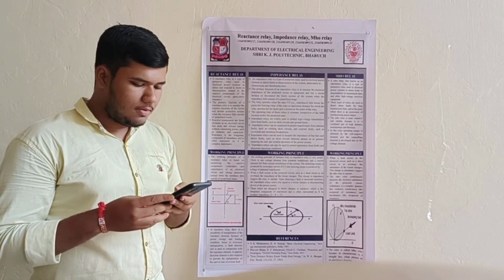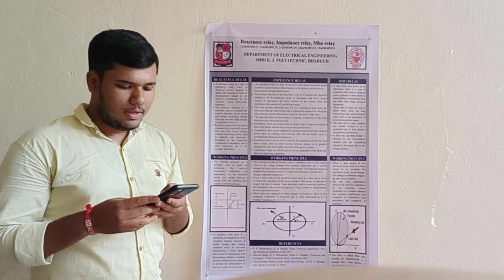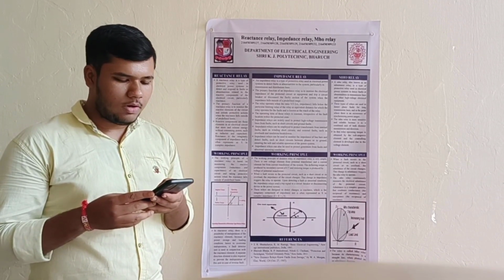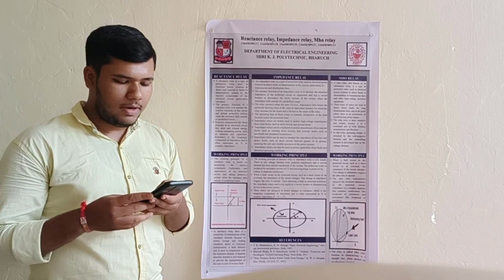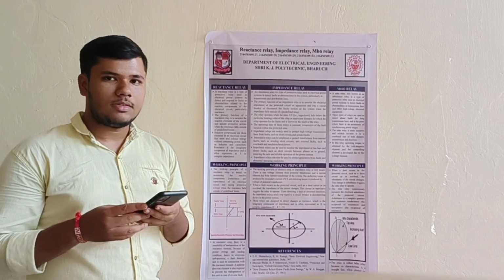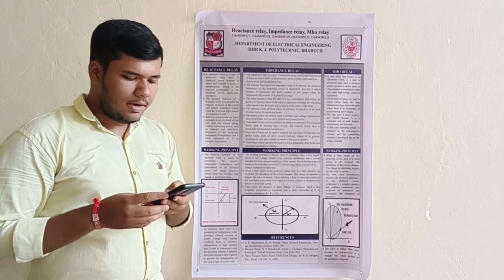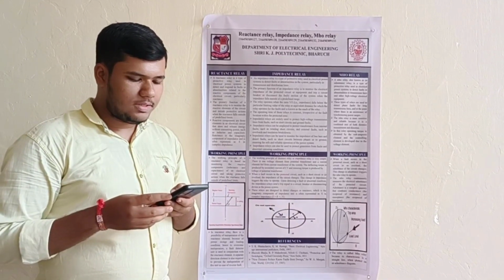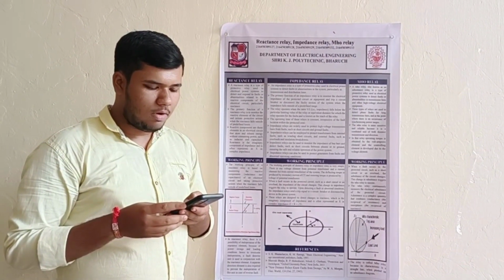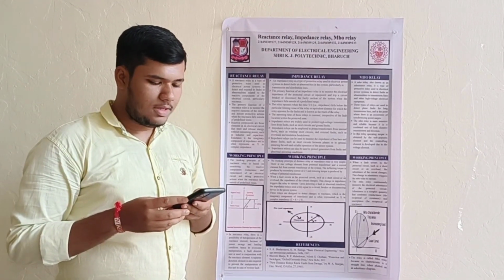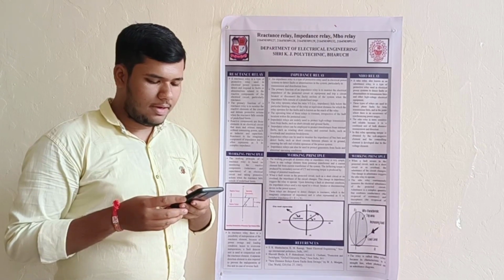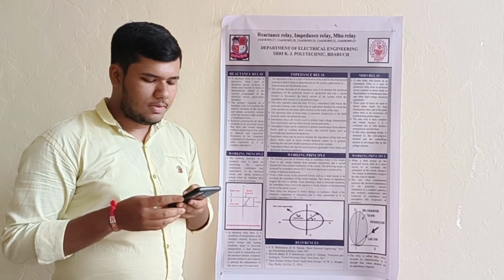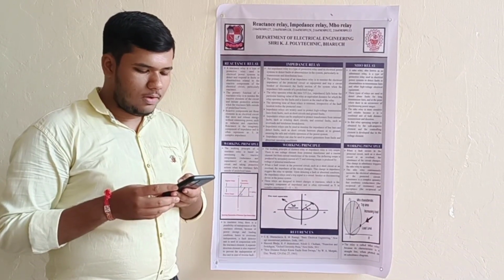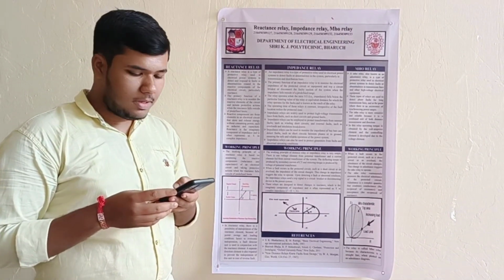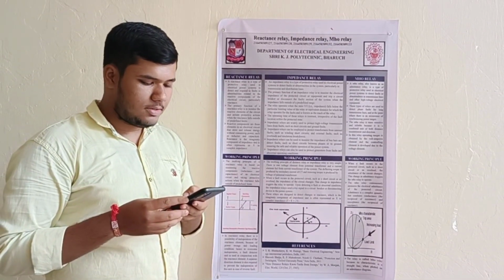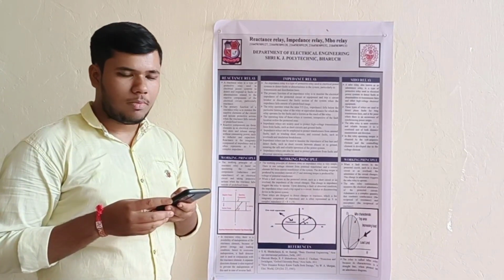Advantages of reactance relay. Number 1. Fast response time. Reactance relays can detect faults and respond quickly, helping to prevent damage to equipment and reduce downtime. The second one is high sensitivity. Reactance relays are highly sensitive to changes in reactance, allowing them to detect even small faults or changes in the system. Third one is simple design. Reactance relays have a relatively simple design, making them easy to install and maintain. Fourth one is wide range of application. Reactance relays can be used in various applications such as power systems, motor protection, and transformer protection.